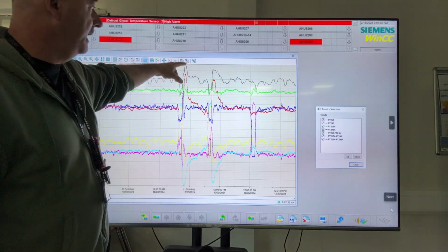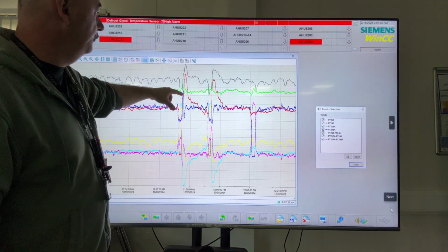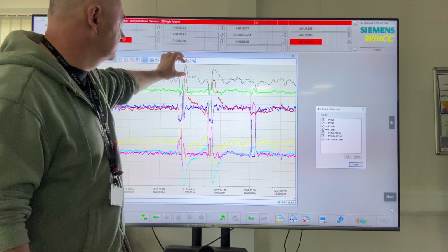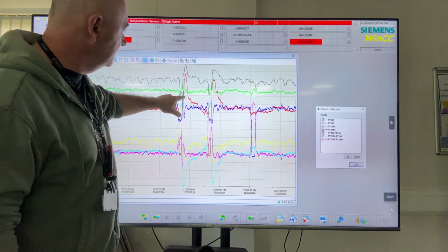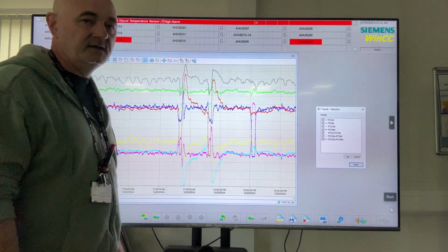If you look very carefully, the black line, which is P215, went very high at one point, and P246 follows it because the SOP says I have to have 25 plus or minus 10. So P246 behaves all right. P215 was the cause. And if you see here, the P246 was above P215A, which is steady, and the pressure difference has been inverted. So the cause was P215.